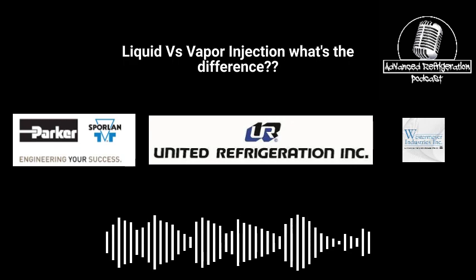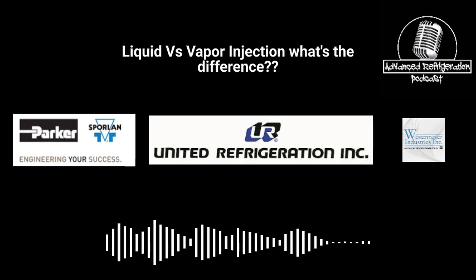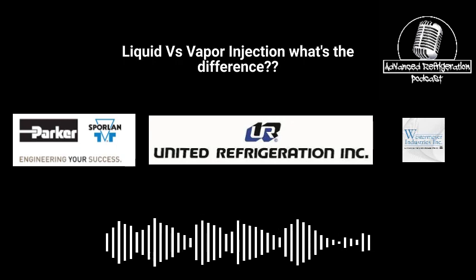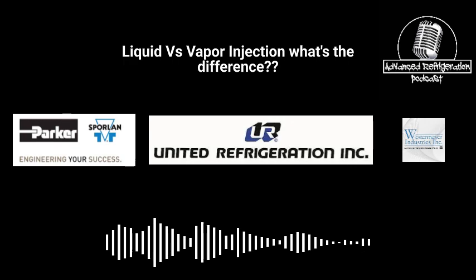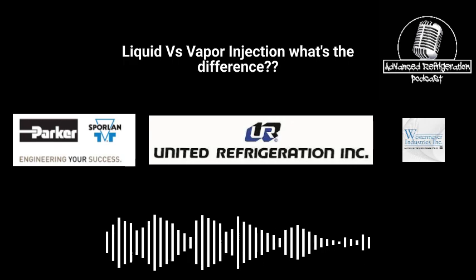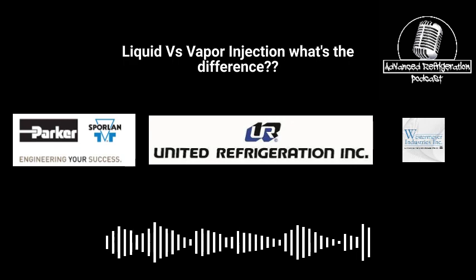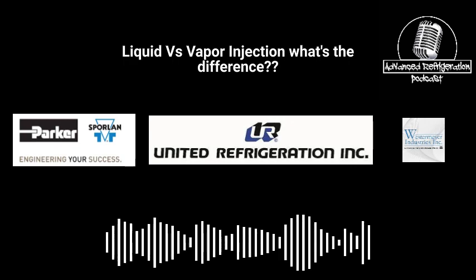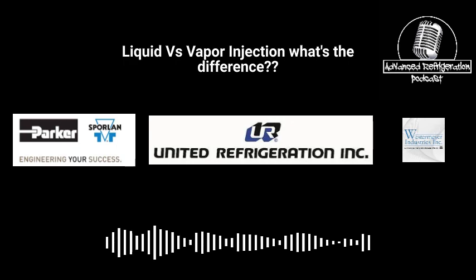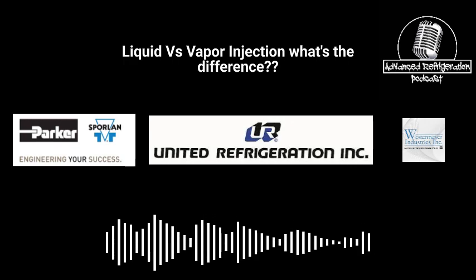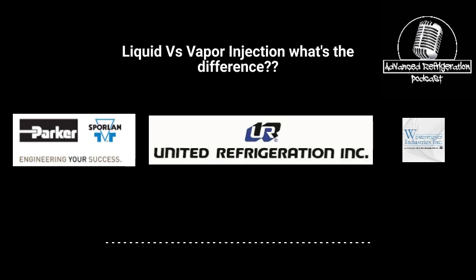You can tell the difference, at least on the Copelands, it's fairly easy. You'll see the hole where it's either going to have vapor injection or liquid injection. If you have liquid injection, that hole's going to be, I think, 1/4 inch or 3/8. If you have vapor injection, it'll be like a half or 5/8 inch entering that compressor. With the scrolls, you'll see the model number on the Copeland compressor. It'll say KVA instead of just KA. The V obviously stands for vapor.